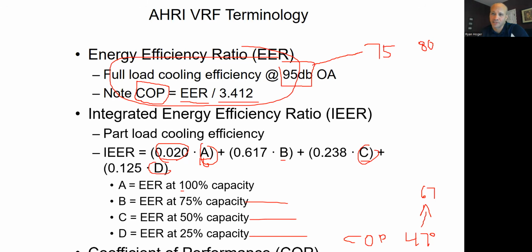Then a few years later, somebody said, yeah, but what does that even tell me? 47, like how often am I even running heat? So someone said, you know what, chop 20 degrees off that, and we'll give you a second rating of COP at 17. So you have EER for cooling, IEER for cooling, then you have COP 47 and COP 17 for heating efficiency. That's 4 ratings for one system.